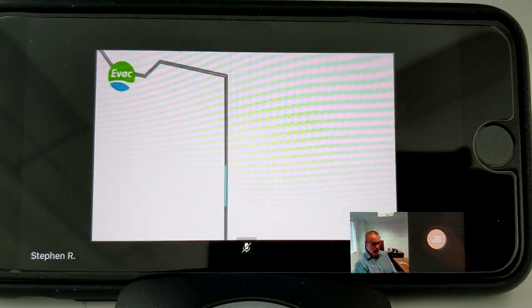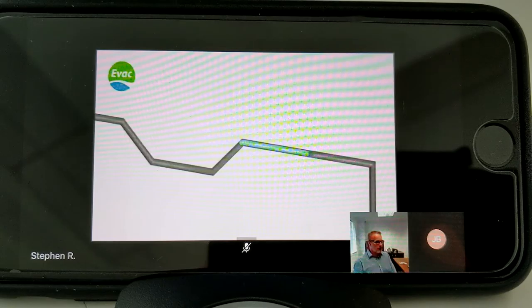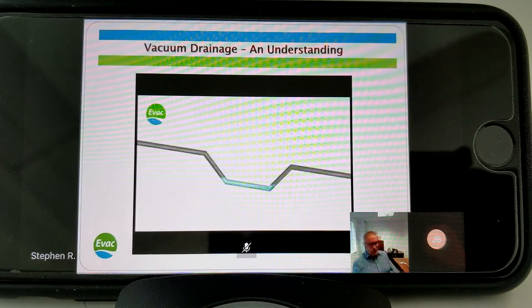There comes our slug of water rising up to high level. I want to stop the video there because what we can see in the pipework looks like a trap - an in-line trap. What that actually is, we call a transport pocket. We have these transport pockets in our high-level pipe every 25 to 30 metres and they serve two main purposes.